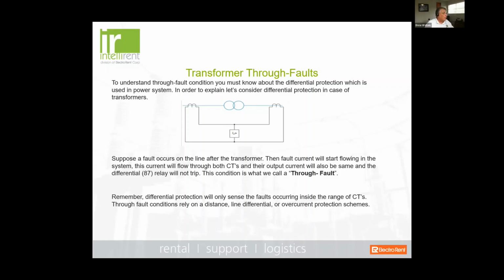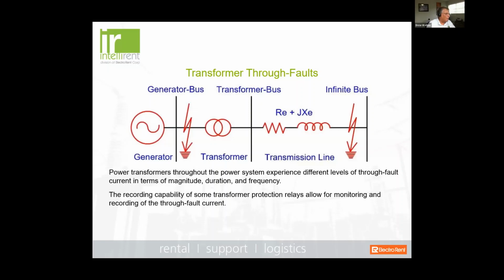current. But with a through fault, let's say this occurs on the line after the transformer, then the fault current will start flowing into the system, and this current will flow through both the CTs, okay? And this is considered a through fault. So remember, differential protection will only sense faults occurring inside the range of the CTs. And that's why we call it a through fault. It's a faulted condition external to the transformer flowing through the transformer itself. So power transformers throughout the power system will experience different levels of through fault current in terms of magnitude, duration, and frequency. And those three things are very important in determining whether we possibly had some mechanical failure.